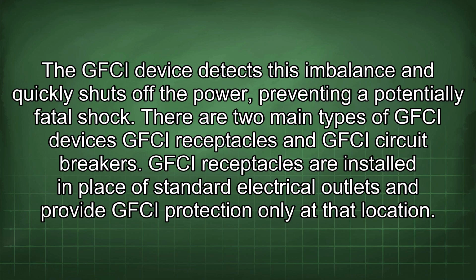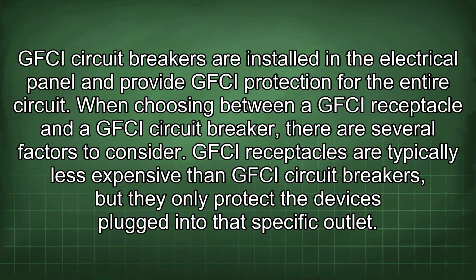There are two main types of GFCI devices: GFCI receptacles and GFCI circuit breakers. GFCI receptacles are installed in place of standard electrical outlets and provide GFCI protection only at that location. GFCI circuit breakers are installed in the electrical panel and provide GFCI protection for the entire circuit.